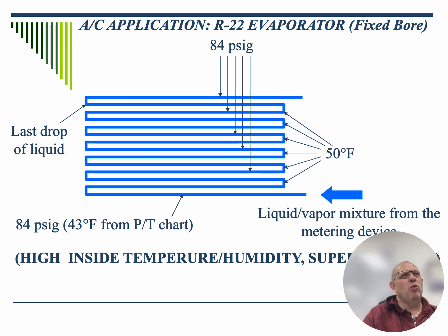Now, we never want to charge an air conditioning system when the temperatures inside the house are exceeding 80 degrees. At that point, we want that system to actually bring the temperature down within the house so that we can go to that system later on with design conditions closer to where they should be, and then actually figure out what's going on with this system. But as we are dealing with higher temperatures, we have an 84 psig suction pressure for our R22 system.